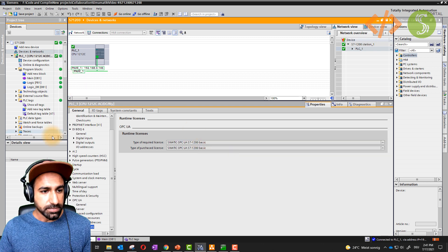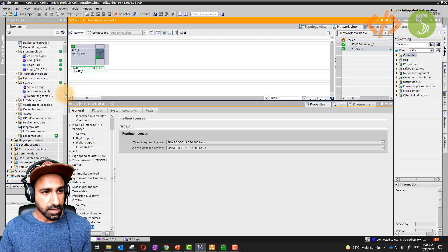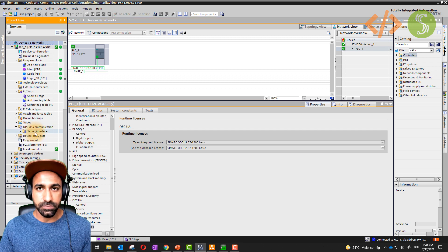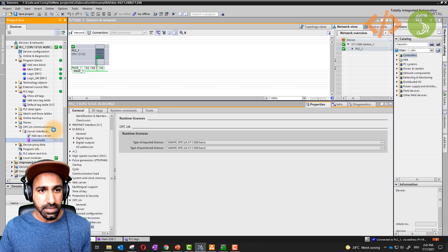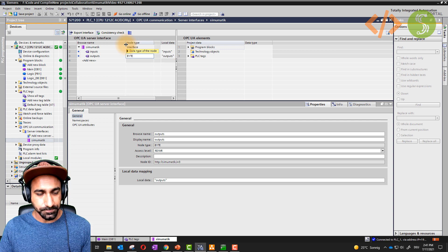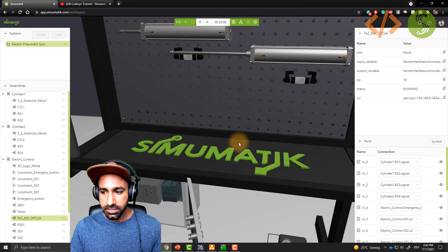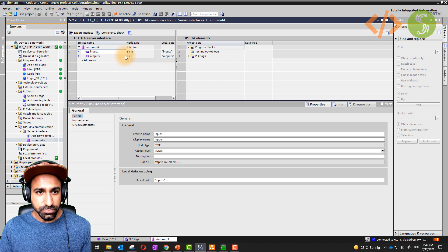The PLC I'm using is S7-1200 1212C. For OPC UA, there is a separate folder: OPC UA Communication. If I open this I get a server interface by default. Click Add New Server Interface — I've already added one and renamed it as Simumatik. Inside this you will see just two tags: inputs and outputs, both are byte type. This is similar to what we did in the CODESYS example. We are reading eight bits from the PLC in Simumatik, so input is a byte and output is a byte.